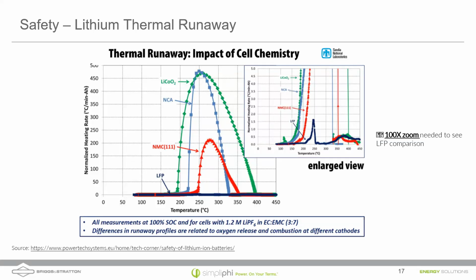So what this graph tells us: they took cells and forced them into thermal runaway. On the horizontal axis, you're looking at temperature. They forced the cells into thermal runaway to get them to off-gas, and that gas coming out of the battery cells is electrolyte, an organic material that can burn. The temperature starts to rise after off-gassing begins.